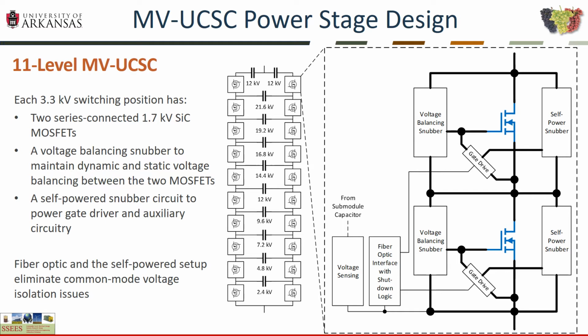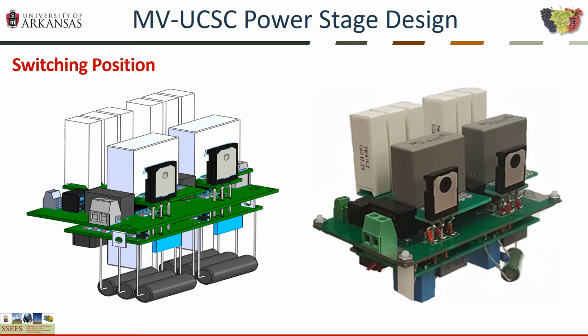So the only thing that we need to connect to the switching position are 4 fiber optics that are carrying control signals and also fault triggering protection signals. Here on the left is the SolidWorks rendition. That's what we normally do before we build it. Here on the right is the built version. Here are the two silicon carbide MOSFETs rated 1.7 kV.